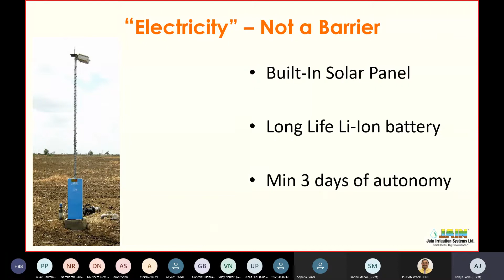So we came up with a solar panel operated external RTU. There is a built-in solar panel. If you look at this RTU, on the top of it there is a 4-watt solar panel, and then we are using a long life lithium-ion battery, which gives us a minimum of 3 days of autonomy. Like if there is cloud and the battery is not getting charged, still for the next 3 days the system will be in operation. So we overcame this barrier by the use of solar operated remote terminal units.